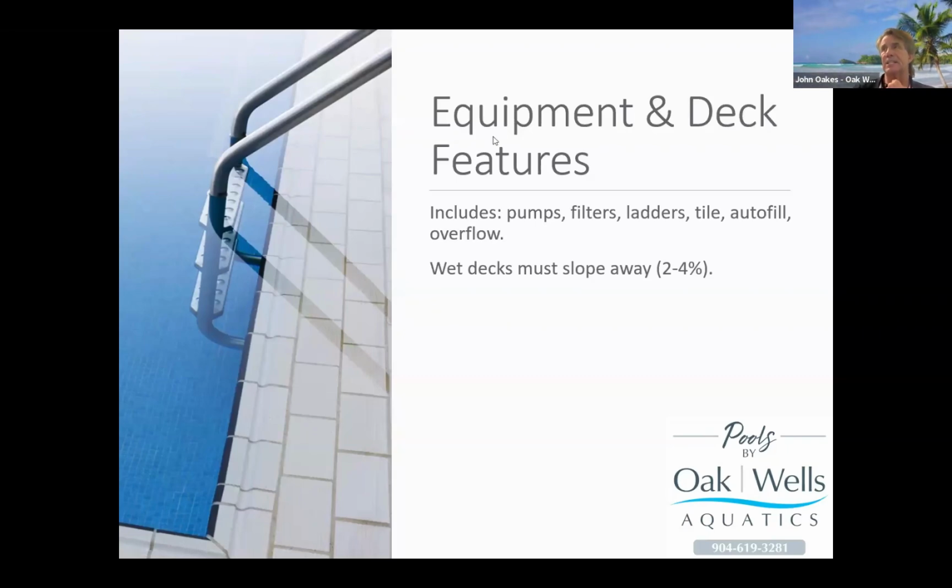And it turns out that the reason that pad area was flooding was that their giant clubhouse had 3 downspouts all on the north end of the building, all dumping into the area that drained into the equipment area. So by rerouting that, we actually solved that problem. But if you're having a pad replaced, it's critical that whoever is doing the work, whether it's Oakwells or field technicians or some other competing company, understands that tank elevation is absolutely critical.